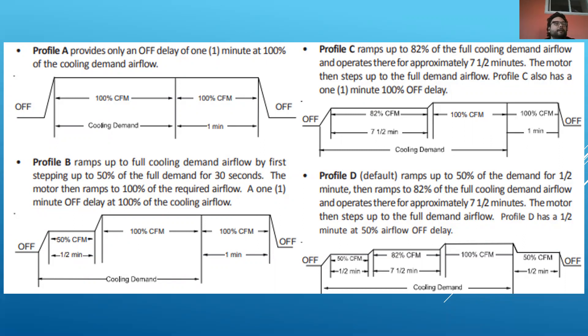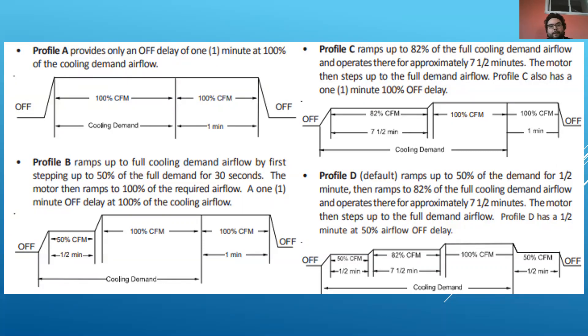Profile D, which is the default, is probably our best option as long as it works for the customer. For the first half minute, we run at 50% fan speed to get the coil really cold, then bump up to 82% — doing as much dehumidification as we can. If we don't meet our set point after about eight minutes, we bump up to 100% fan speed. My recommendation is to set it to Profile D, but talk to your customers and use your judgment to figure out what works best for the equipment.